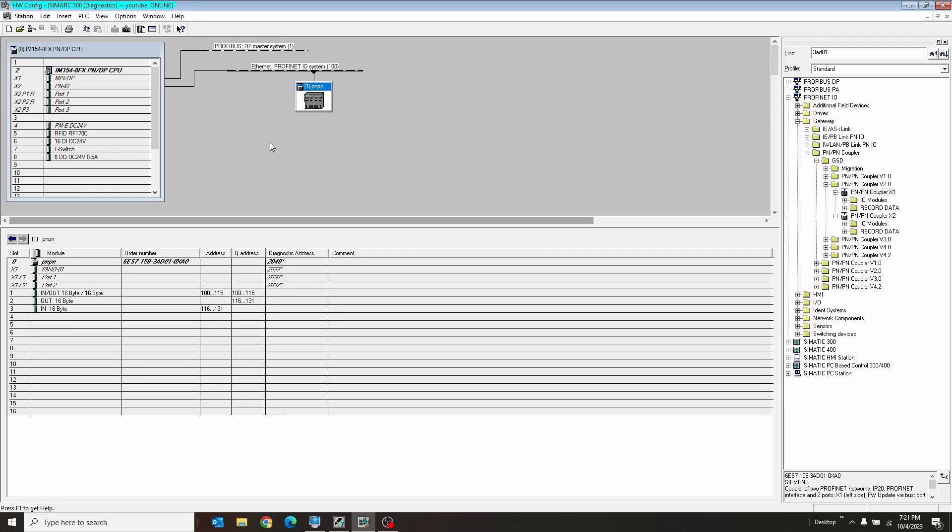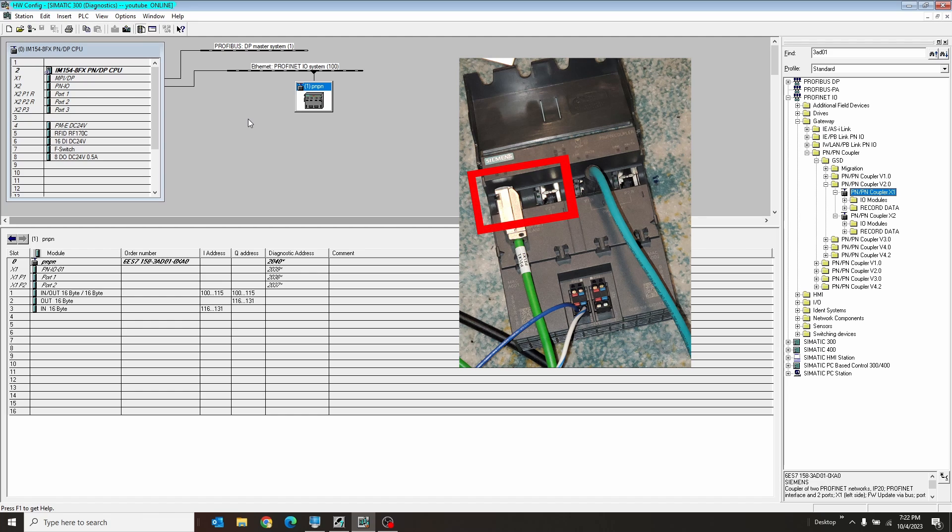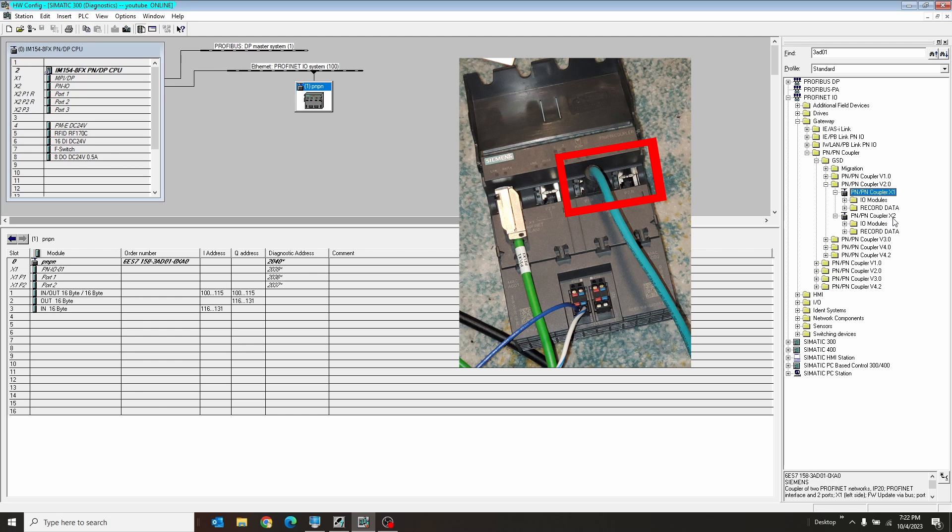The PN/PN coupler has two ports on it. It actually has four because each port pair acts as like a mini two-port switch. So the first port pair of the PN/PN coupler will be called X1 and the second port pair will be called X2. And it is important when you put these things into your project which one you choose.